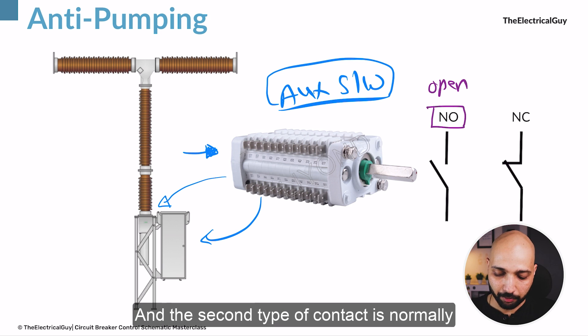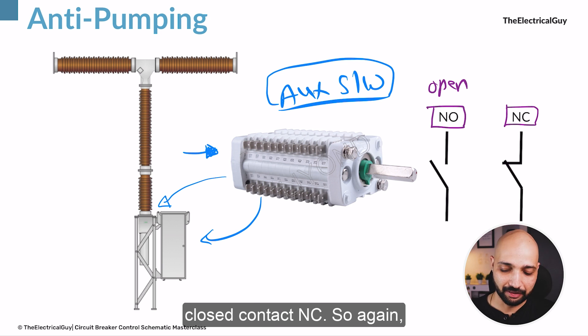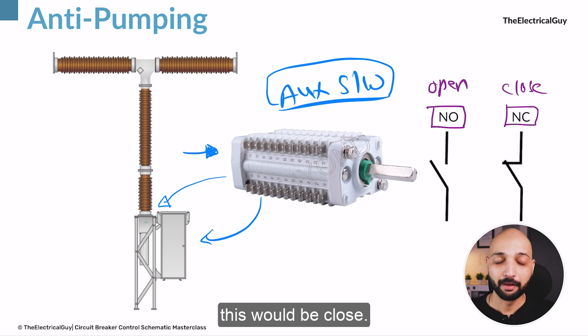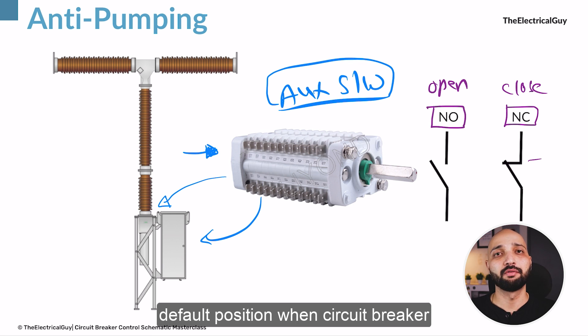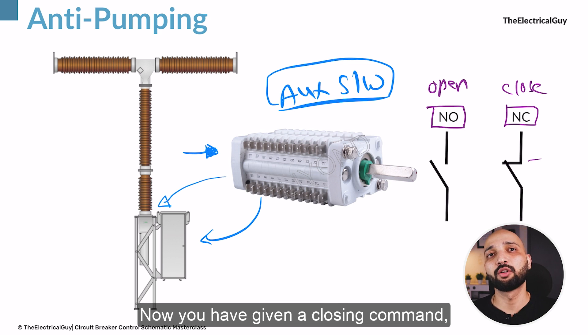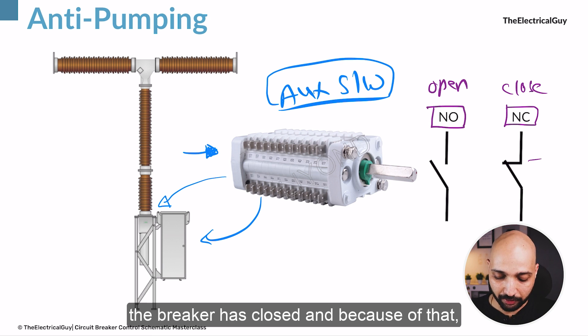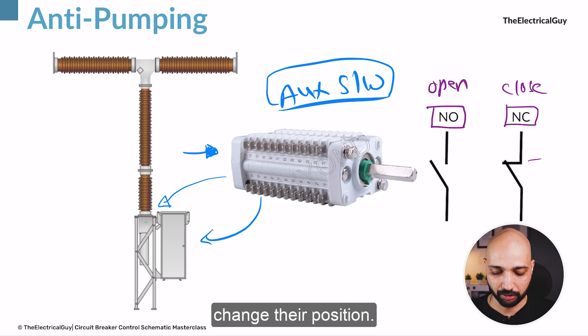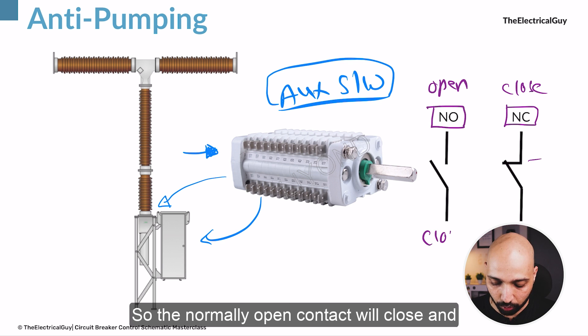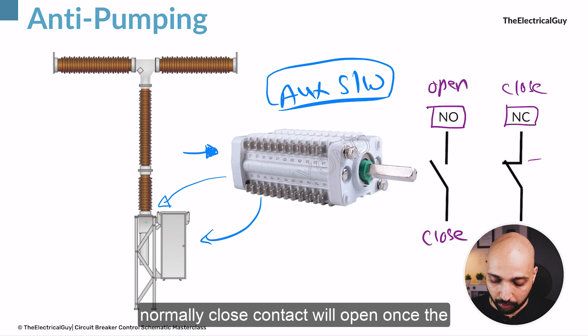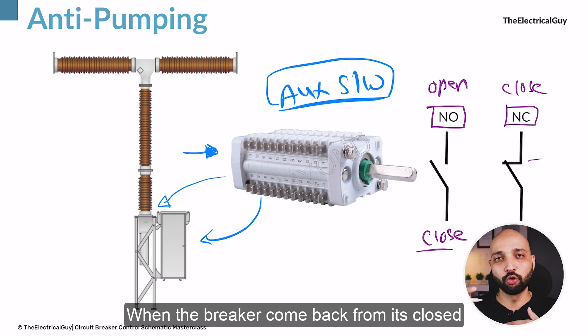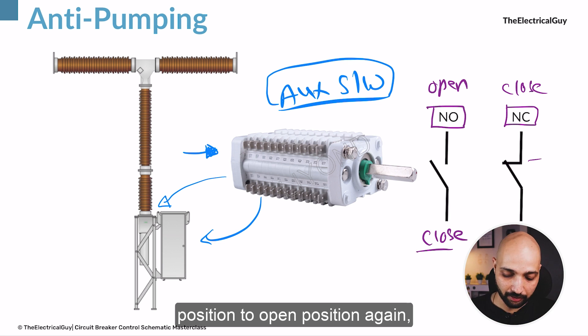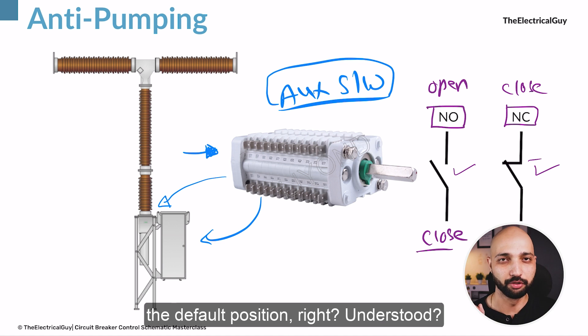The second type of contact is the normally closed contact (NC), whose default position is closed. These are the default positions when the circuit breaker is in the open condition. When a closing command is given and the breaker closes, these contacts also change their position — the normally open contact will close and the normally closed contact will open. When the breaker comes back from closed to open position, the contacts return to their default positions.